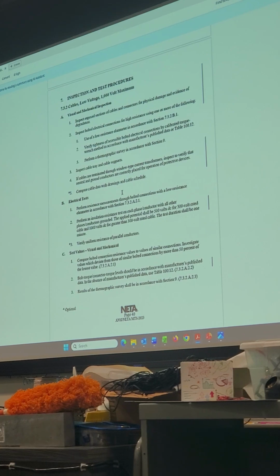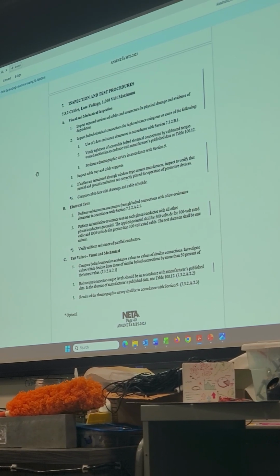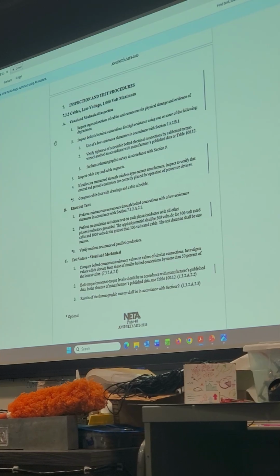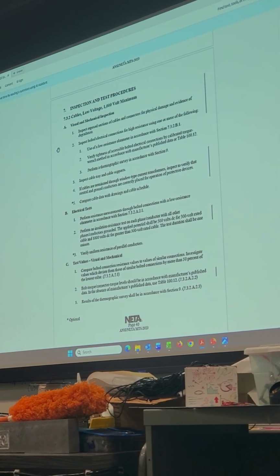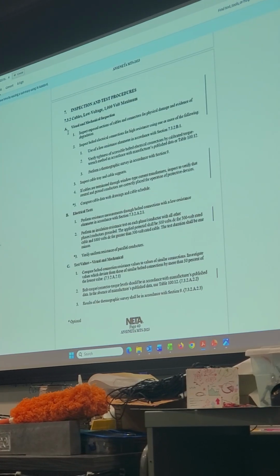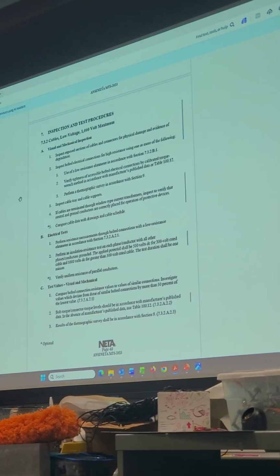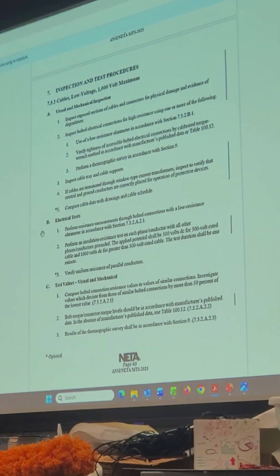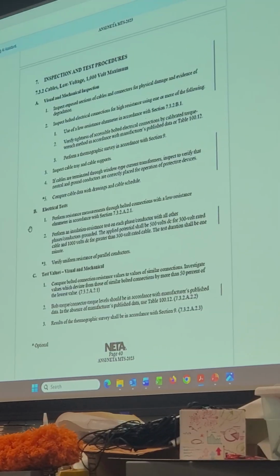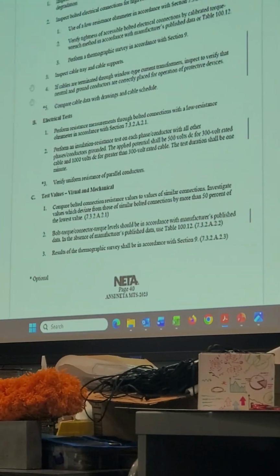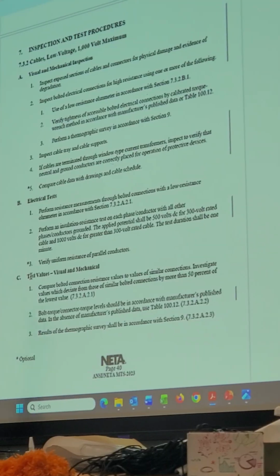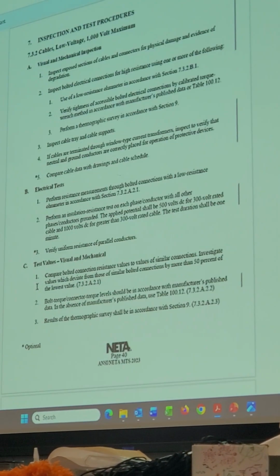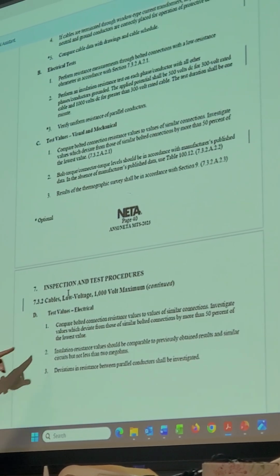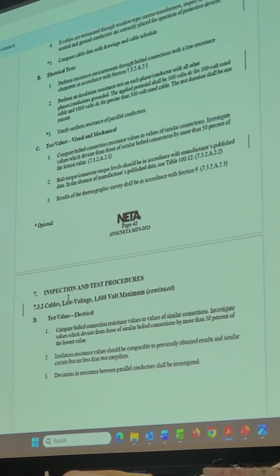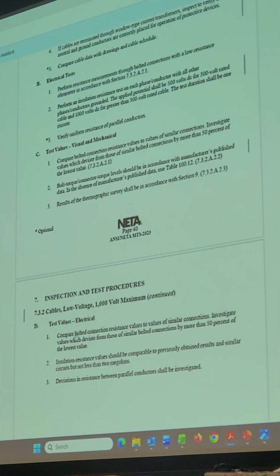So if you're looking along here, take a look at how the progression goes. 7.3.2 is your low voltage cables, 1000 volt max. You'll see A is the first header for visual mechanical inspection. Before we even go into a deep dive there, you'll see that B is for your electrical tests. C is for your test values for visual mechanical, so C is kind of the answer to A. And then you'll notice that D is the answer to B right there. So it's test values, electrical. So: visual mechanical, electrical, test values for visual mechanical, and then test values for electrical.